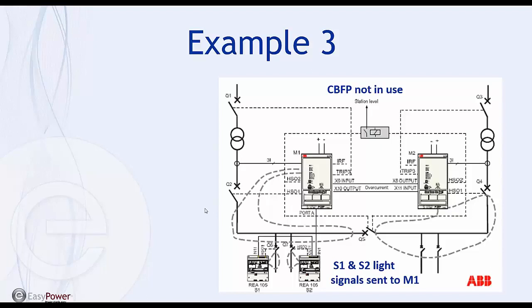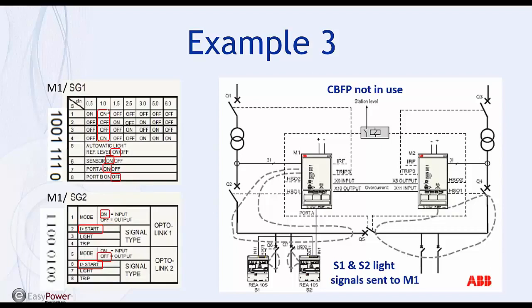So we're going to take a look at the switch settings. 1 amp per unit of the nominal. We're using backlight compensation this time. Sensors activated. This time we're just using port A, so we'll have that switch on. Port B is off. We're using the OptoLink this time, so we'll have the switch on for the main 1, which means that we're receiving current, and we're transmitting current here on X10 for OptoLink 2.